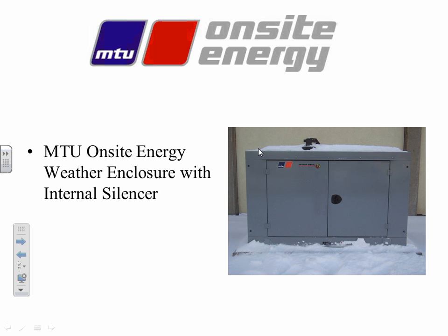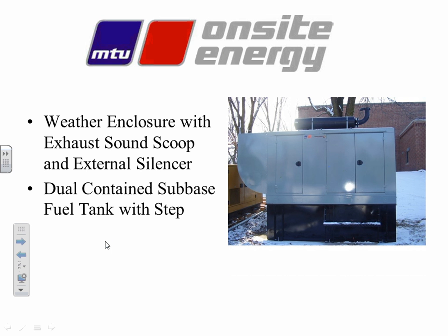Well, you don't have any motion with a generator that's just standing there. So they reverse the fan, and it's a pusher type fan. So if it's sitting here, this fan is pushing out this way. That creates a negative pressure inside the enclosure, so it sucks in the air from wherever. That makes it real flexible where to put the inlet louvers, too, as we'll see in another second.